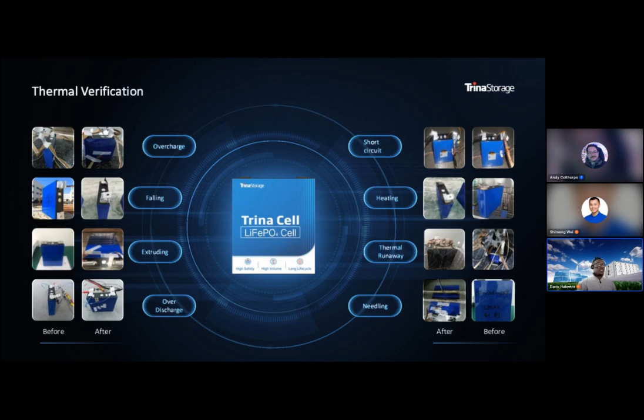We then go on to a 9540A test, where the aim is to put that device under test into thermal runaway and evaluate how it behaves going forward during operation. I picked UL 9540 as one of the product certifications we go through - in essence, this is a test that validates or looks at how thermal runaway could occur in the system, and if that propagates. The intention is to make sure this does not propagate across the whole system.